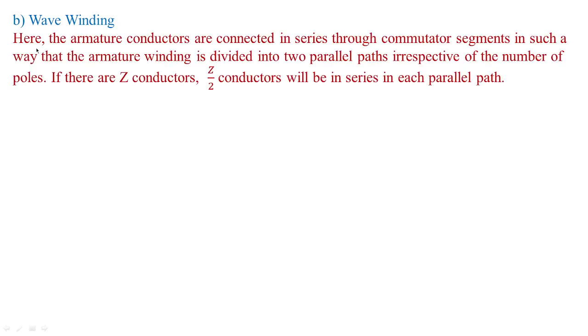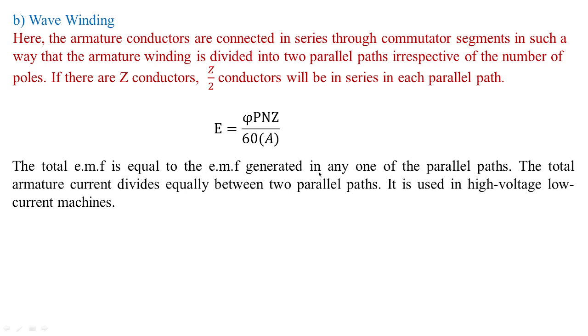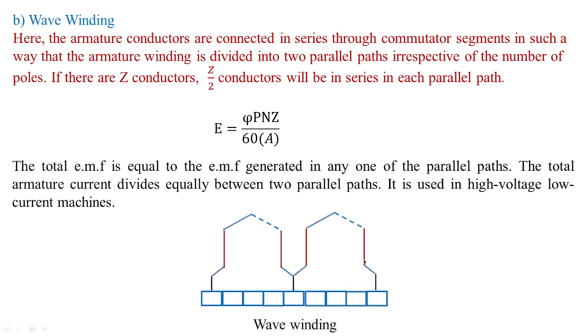Next is the wave winding connection. Here, the armature conductors are connected in series through commutator segments in such a way that the armature winding is divided into two parallel paths, irrespective of the number of poles. If there are Z conductors, then Z/2 conductors will be in series in each parallel path. The total EMF equals the EMF generated in any one of the parallel paths, and the total armature current divides equally between the two parallel paths. This type of wave winding is generally employed for high voltage and low current machines. If you take an overview, the winding takes the form of a sinusoidal wave — that is why this connection is known as wave winding.